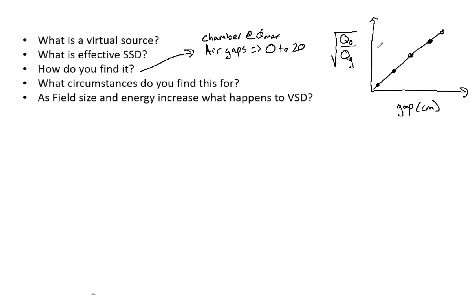To actually find the effective SSD, you have to use the equation: one divided by the slope that we just determined, and then subtract d-max. That is going to give you your effective SSD.